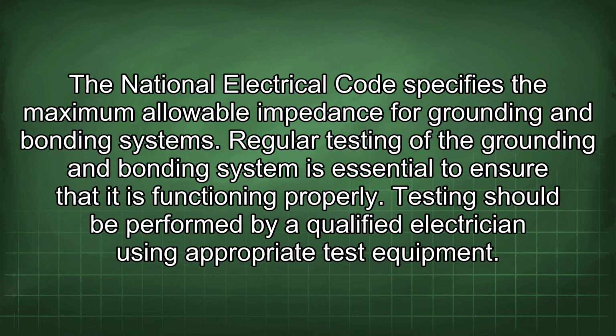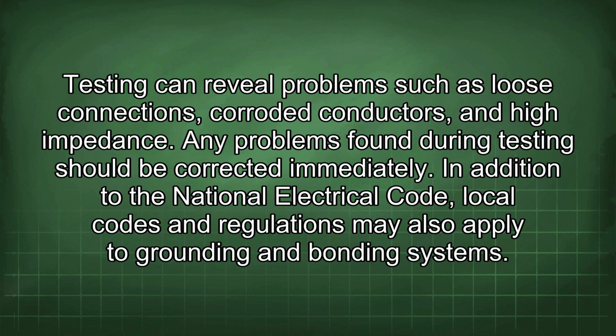Regular testing of the grounding and bonding system is essential to ensure that it is functioning properly. Testing should be performed by a qualified electrician using appropriate test equipment. Testing can reveal problems such as loose connections, corroded conductors, and high impedance. Any problems found during testing should be corrected immediately.